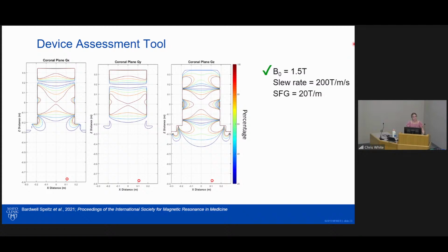Elena, is it just the ends of the leads that you're worried about heating, or is there heating elsewhere that's a concern? Our focus was just the lead tip, at the electrode, where the maximum heating is. If you remember from my dissertation, it's all calculating a line integral along the lead, so it's just summing all the way till you get to the end. That's where it's going to be at its maximum. That could potentially affect the tissue around that electrode, so you would care about what the temperature rise would be at that lead tip.